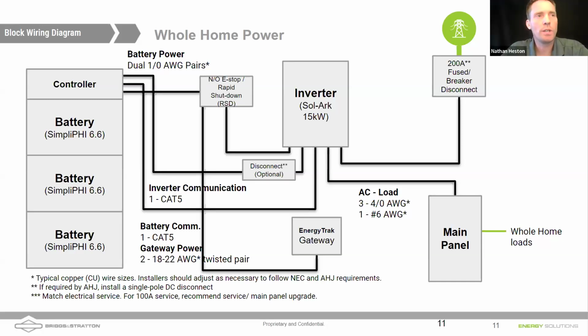And I actually wanted to talk just a little bit while we're here on the PCS control that Sol-Ark offers through their software. Typically with the 120% rule, you are limited in how much you can backfeed to a loads panel, right, based on your busing. And I know that you can get specialized buses that are larger. For instance, if you're doing a 100 amp panel, right, you can get 120 amp buses on that. But what does PCS control allow us to do with Sol-Ark?